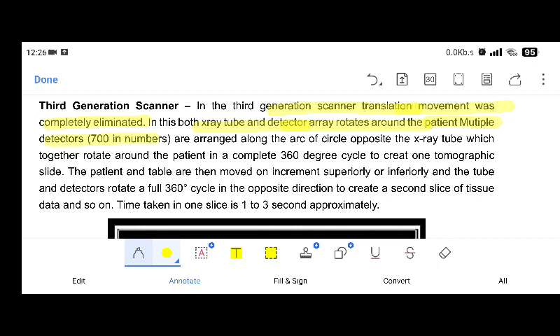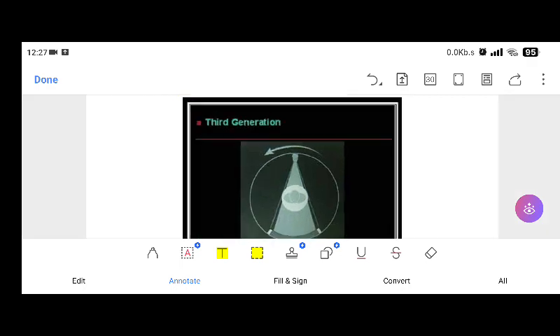Multiple detectors, 700 in number, are arranged along the arc of a circle opposite the X-ray tube, which together rotate around the patient in a complete 360-degree cycle to create one tomographic slice. The patient and table are then moved one increment superiorly or inferiorly. The tube and detector rotate a full 360-degree cycle in the opposite direction and create a second slice of tissue data, and so on. The time taken is approximately 1 to 3 seconds per slice. And this is the third generation.